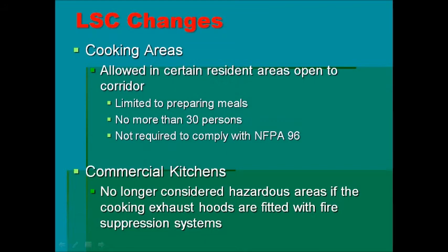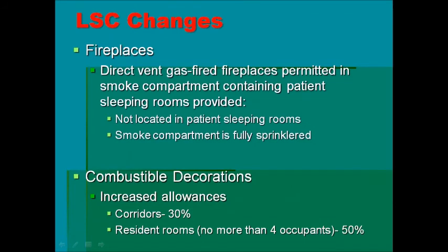The 2012 edition of the code and newer code editions of life safety allow you to have open cooking arrangements in resident care areas within your facility. And they've downgraded the hazard condition of a kitchen to not being a hazardous area if appropriate fire protection measures are in those places. You know, we want to make a home-like environment in our healthcare facilities, and fireplaces and decorations can be part of all that, but there are some elements that you've got to be aware of.